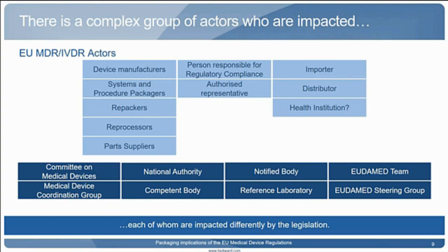You have your system and procedure packagers, which we've discussed on the previous slide, your repackers, your reprocessors, and also parts suppliers. And all of these, including in some cases the parts suppliers, in the new legislation are considered as device manufacturers in their own right.